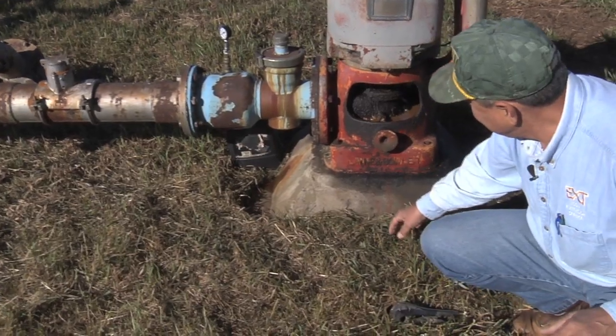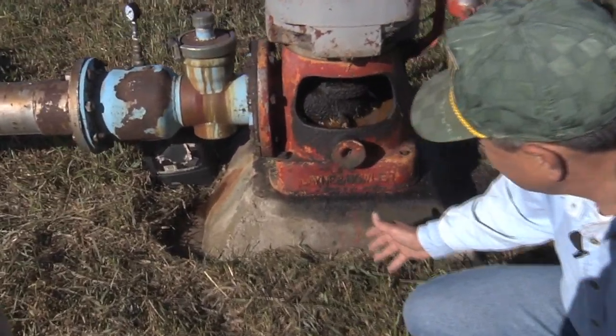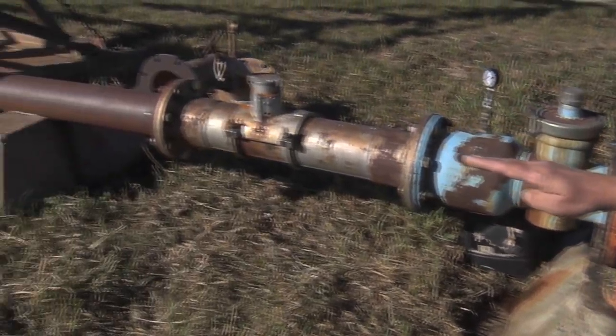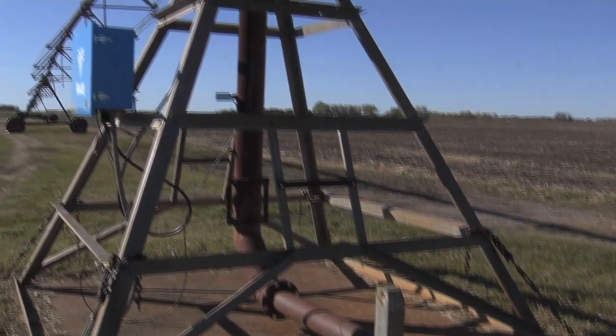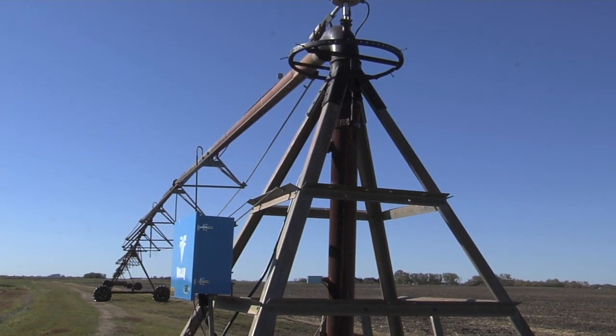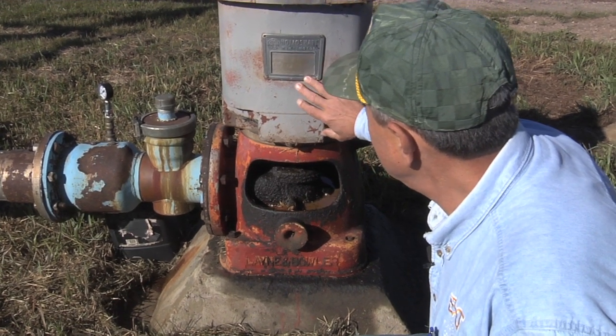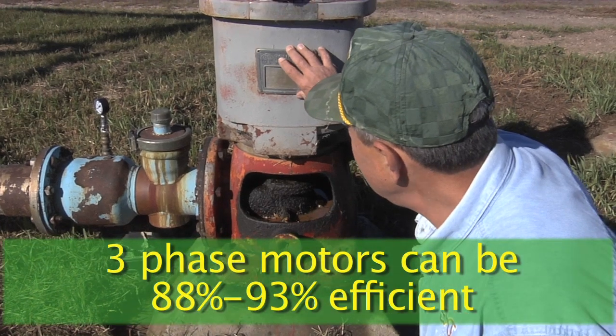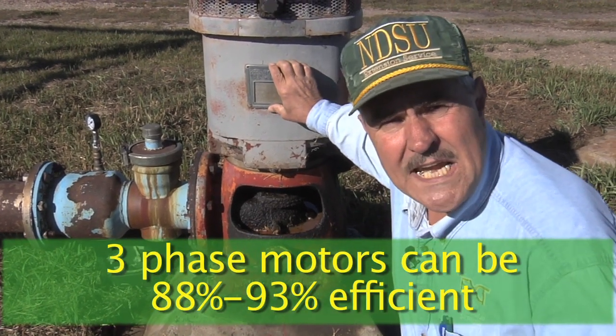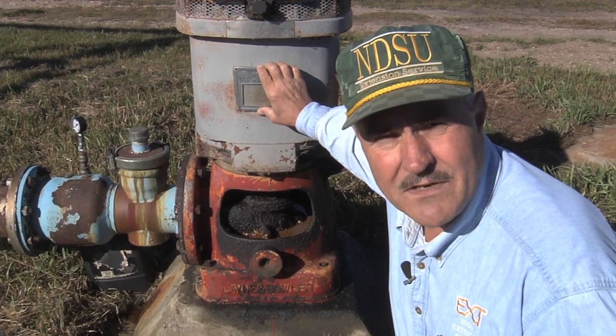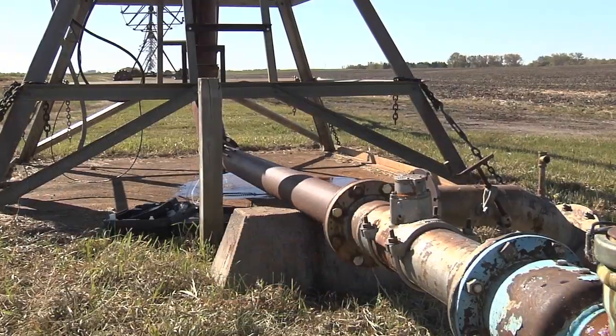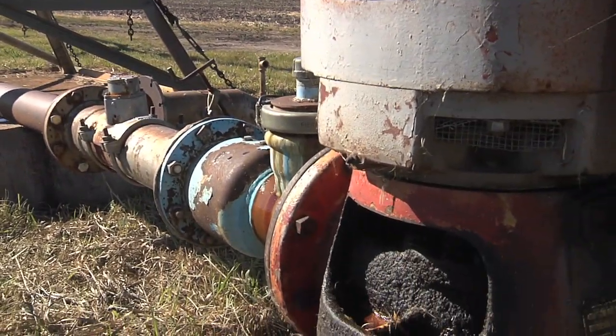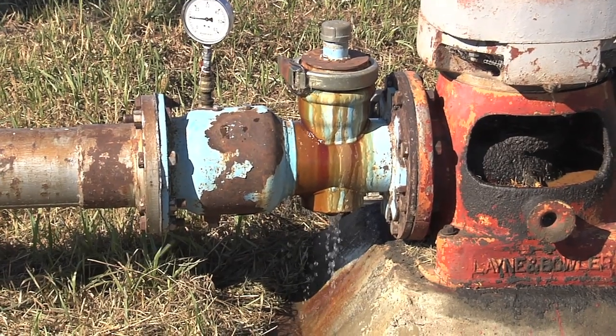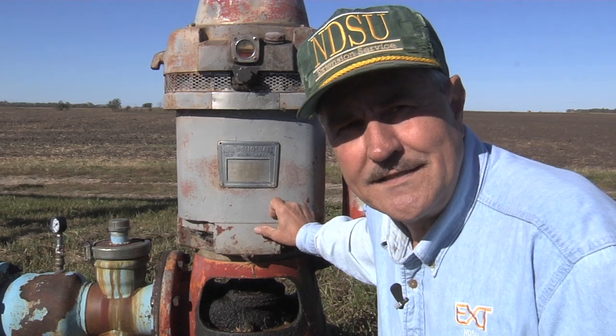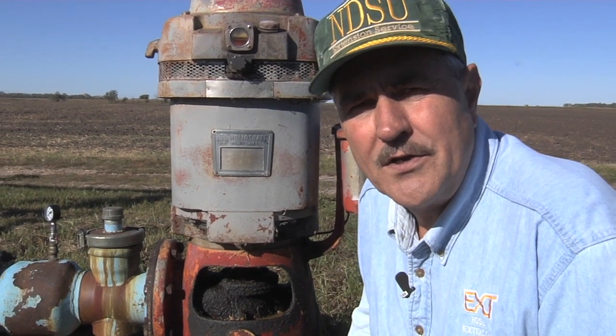The pump is down in the well, and it lifts the water up. As you can see, it goes off over here, goes up to the pivot point, and then from there it goes out in the pivot. These are large asynchronous induction motors. They're very efficient. Typically, these larger three-phase motors like this can be anywhere from 88 to well over 92, 93% efficient. They're very good pumping, but there are some inefficiencies, and over time you can get wear on the impellers, and that can cause inefficiencies. And so we're going to do a pump efficiency test on this system to find out how it's performing against what we consider a very good operating system.